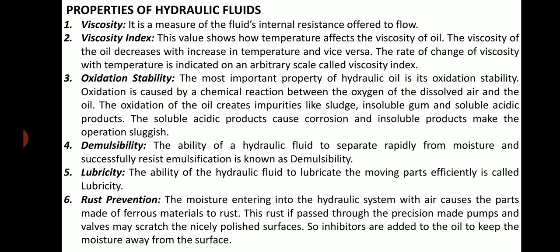Oxidation Stability: The most important property of hydraulic oil is its oxidation stability. Oxidation is caused by a chemical reaction between the oxygen of the dissolved air and the oil. The oxidation of the oil creates impurities like sludge, insoluble gum, and soluble acidic products. The soluble acidic products cause corrosion and insoluble products make the operation sluggish.